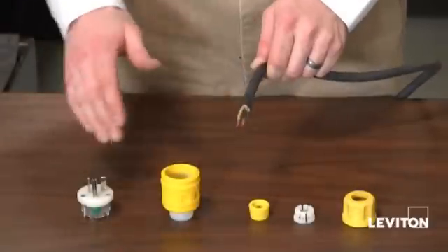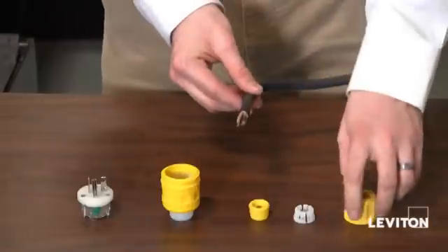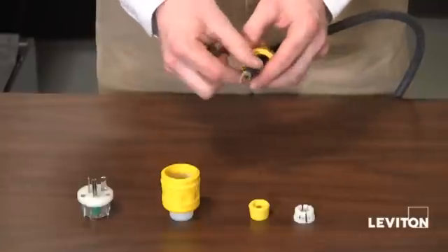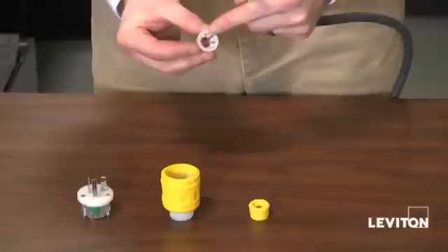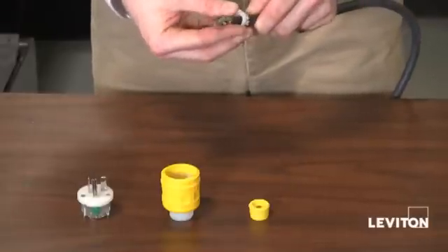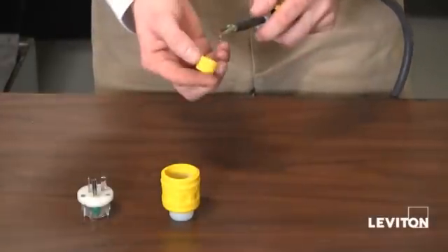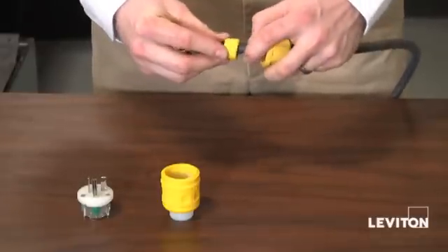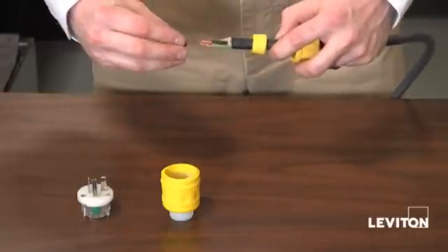In order to ensure the integrity of the plug, it's important that each individual piece goes on in the correct order. First, the nut. You want to make sure that the threads are facing towards the end of the cord. Next, the strain relief washer. Here, you want to make sure that the circular piece is facing towards the end of the cord, just like that. Now I'm going to go ahead and put on my rubber bushing. Now you will notice that the rubber bushing, one side is smaller than the other. You want the smaller side facing towards the end of the cord.